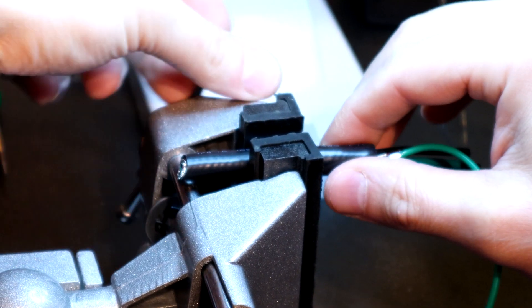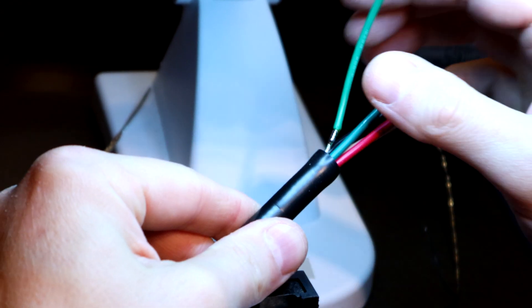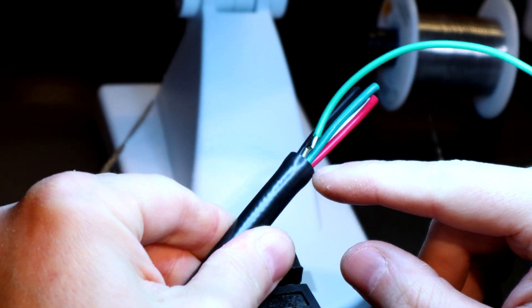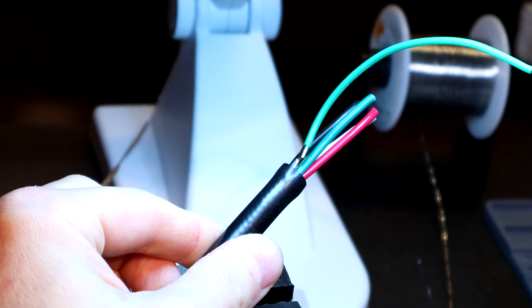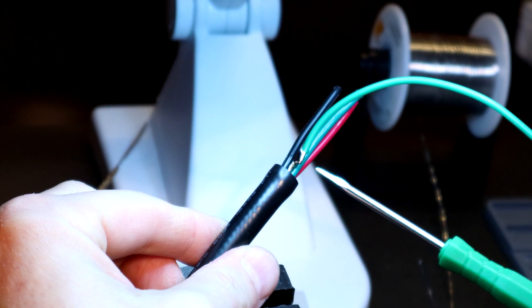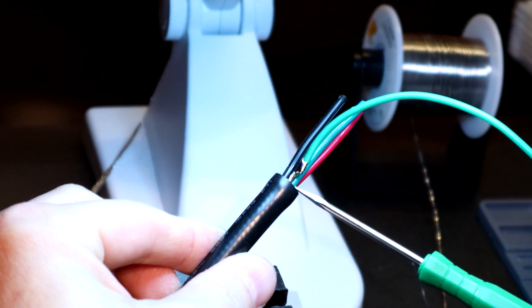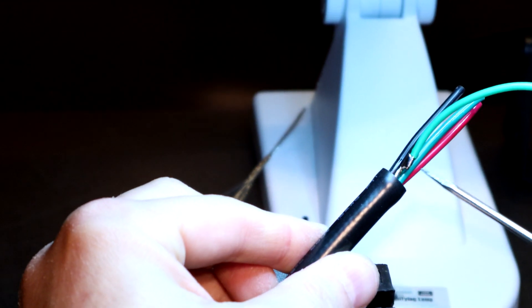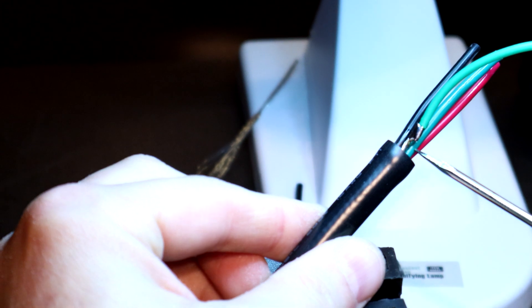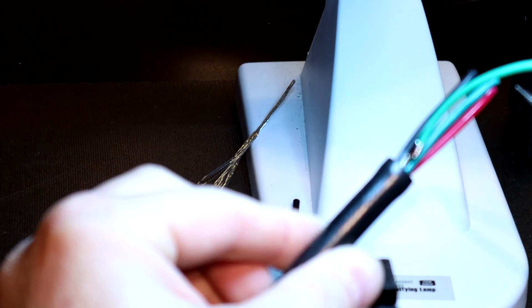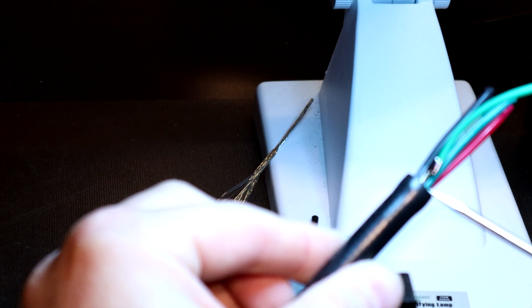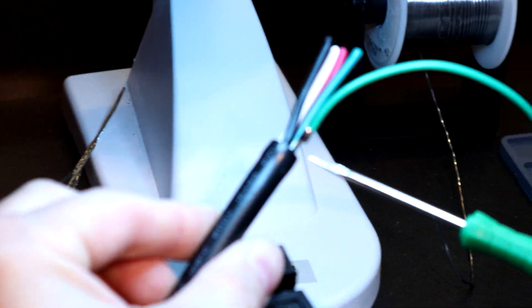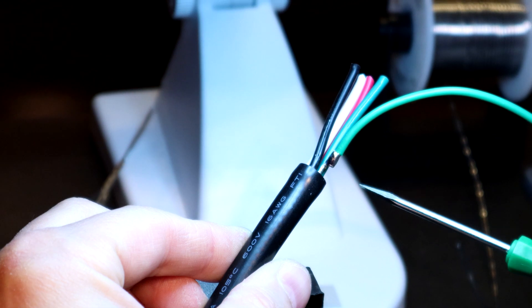Now, looking at the cable end, you can also see, and this is something I get asked too, you see no exterior tin-braided copper exposed. When you're working with shielded cable, the biggest thing you want to pay very close attention to for safety is making sure that all of your tin-braided copper and mylar foil is embedded in the PVC casing because we want to avoid it ever creeping out, potentially poking into our exterior PVC casing of the leads and also potentially making contact with conductors which are carrying power. If a ground actually makes contact with a conductor, you would have what's known as a dead short, and that could be catastrophic in terms of fire, injury, or potential death.